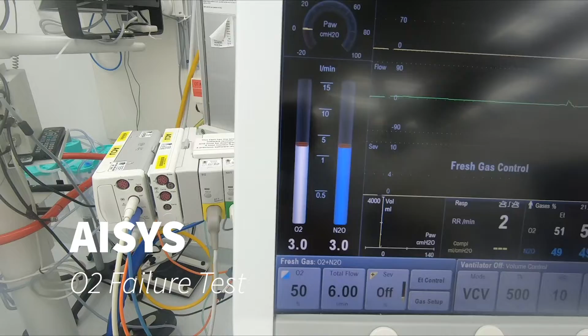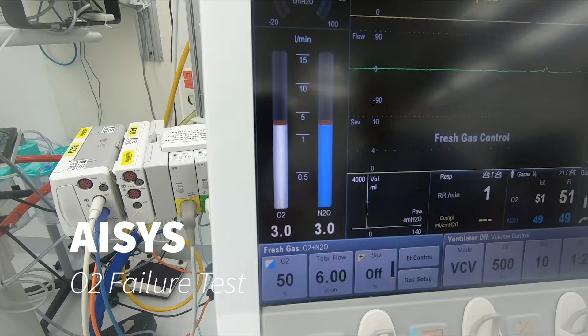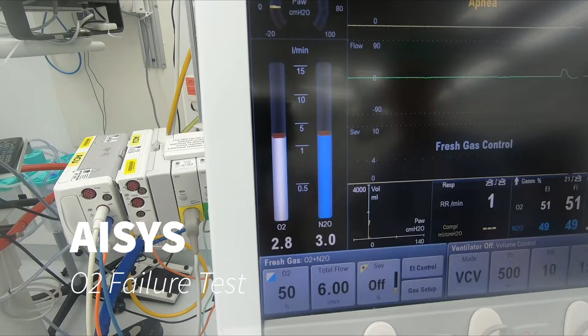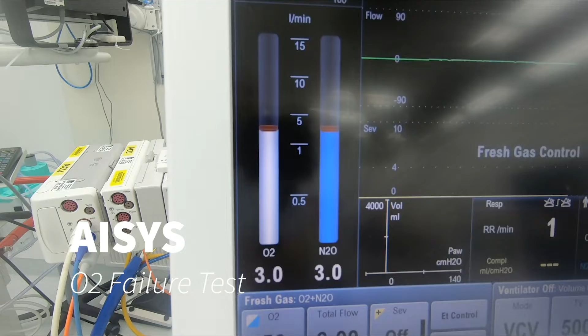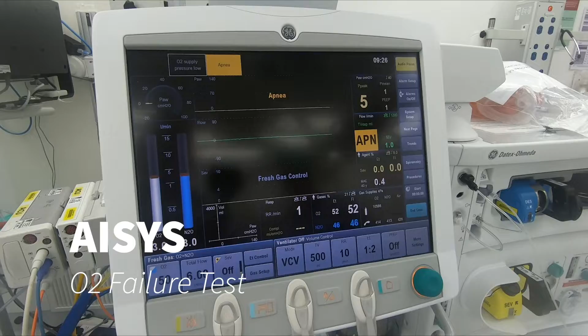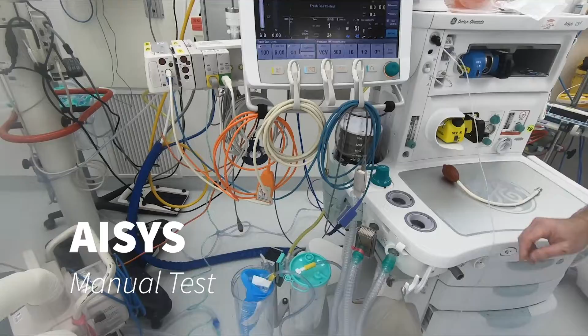So we're going to simulate an oxygen failure. So the oxygen is disconnected now. We sometimes use the flash just to... Oxygen supply fail, gas supply. Yep. Open oxygen cylinder. Okay. And we're back in business. And we've switched our cylinder up as well. Perfect. So I've seen it once.